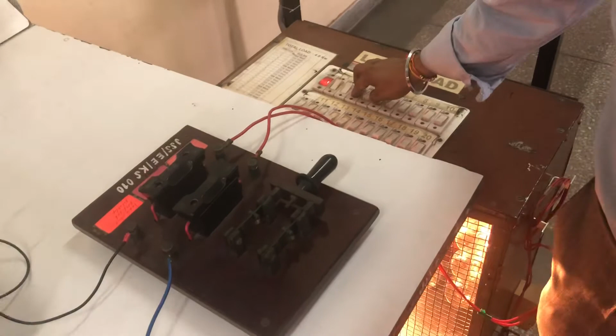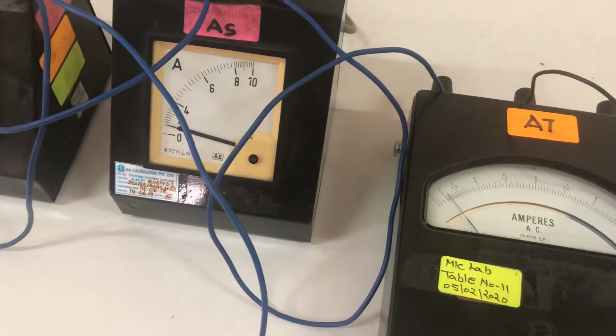It is showing 2 ampere. And what is the test ammeter reading? I am getting more than 2 - it is 2.2. Here you should check the upper scale reading because we are connecting it to 0 to 10 ampere. So standard we are getting 2, and in the test ammeter we are getting 2.2.